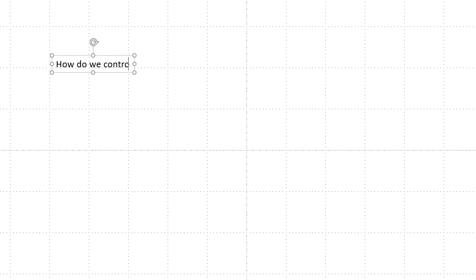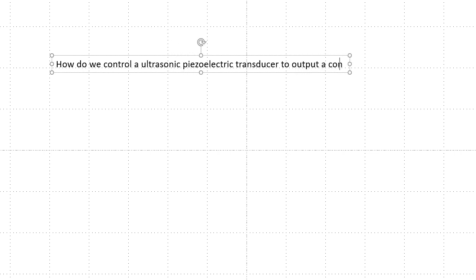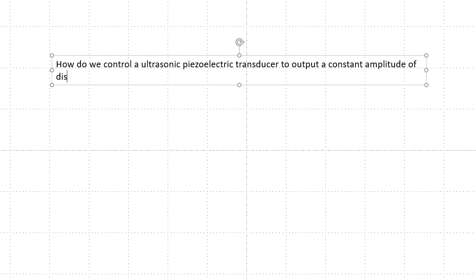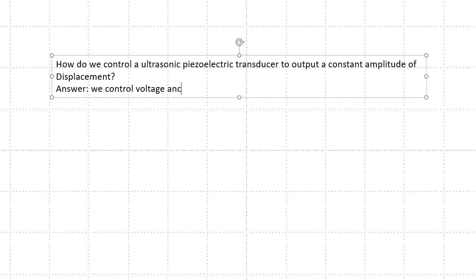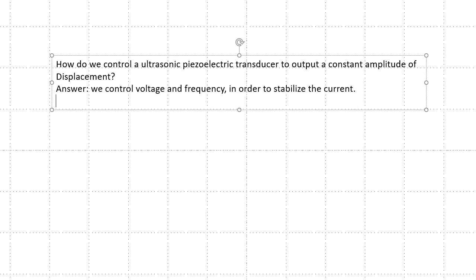How do we control an ultrasonic piezoelectric transducer to output a constant amplitude of displacement? The answer is we control voltage and frequency in order to stabilize the current. The current directly relates to the displacement output of the transducer.